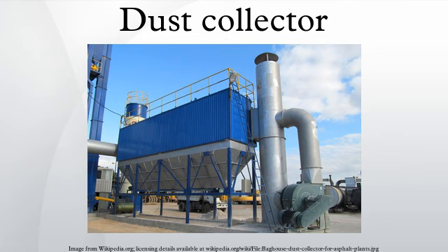However, the selection of a dust collector should be based on the following general factors. Dust concentration and particle size: for minerals processing operations, the dust concentration can range from 0.1 to 5.0 grains of dust per cubic foot of air, and the particle size can vary from 0.5 to 100 micrometers in diameter. Degree of dust collection required.